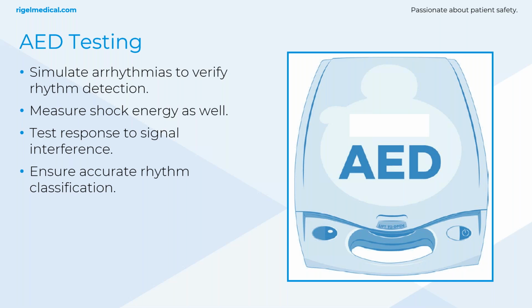We also need to measure the shock energy as well. We need to make sure that it's delivering the correct energy levels. And then we're also, and this is something else that sometimes gets missed, testing the AED's ability to analyze ECG signal quality. How well will it filter noise out? And it's part of the standard for defibs.